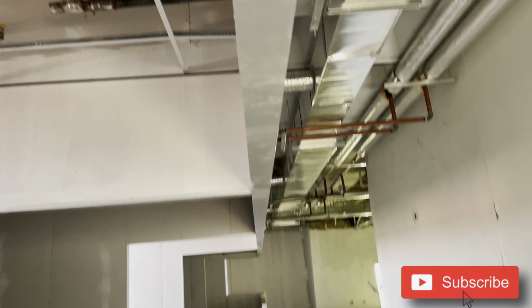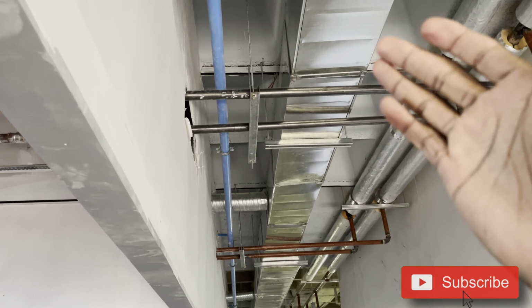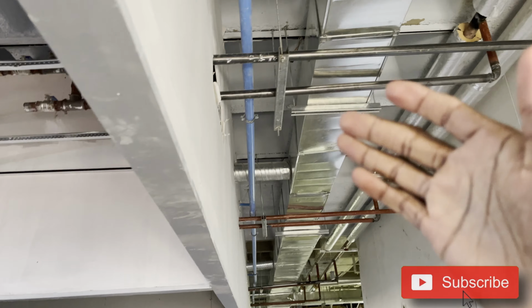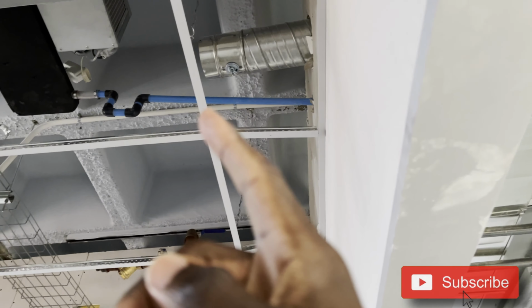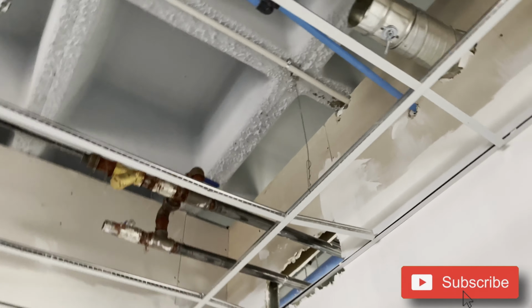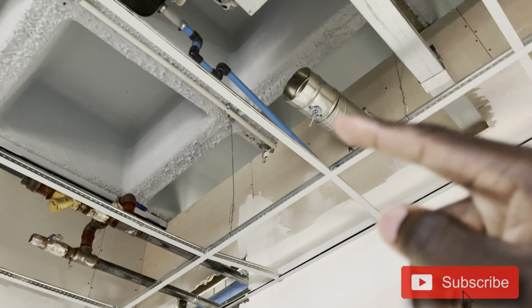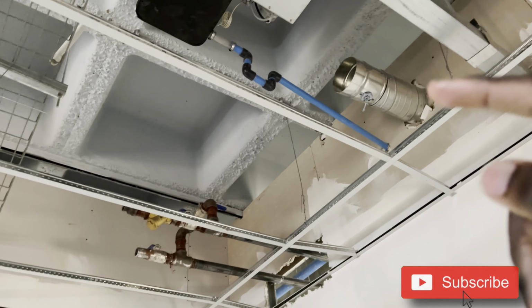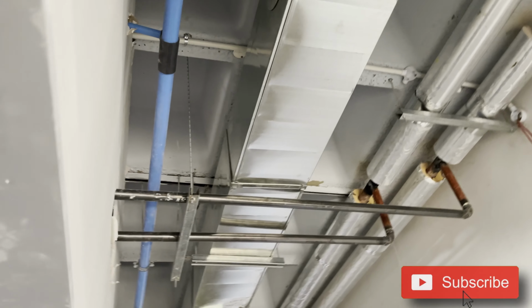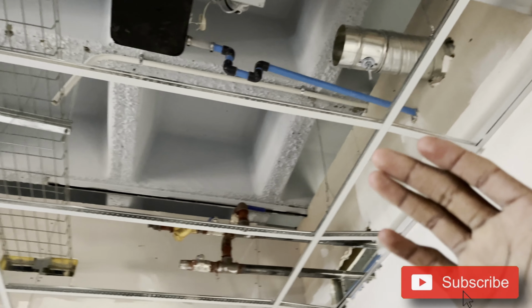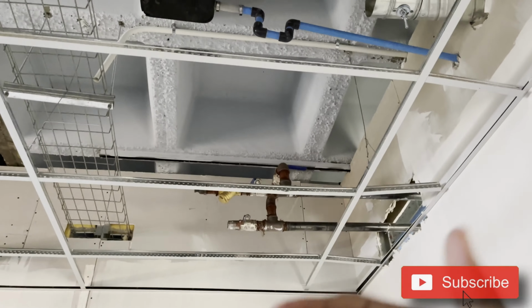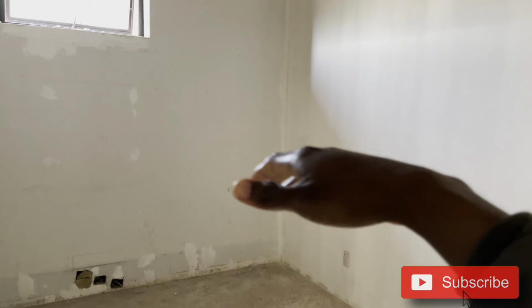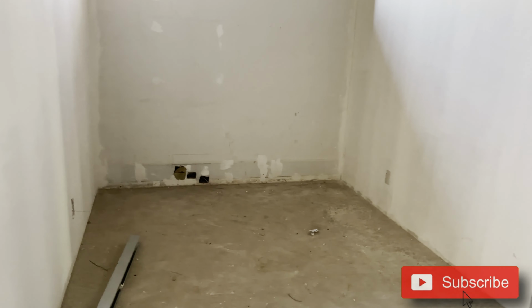So we have an uninsulated duct that you see over there, and each section branches off from there, with balancing dampers at this point. The purpose of a balancing damper is to regulate the amount of air that flows from the main supply box into the building, providing a regulated amount of air per second into this office space.